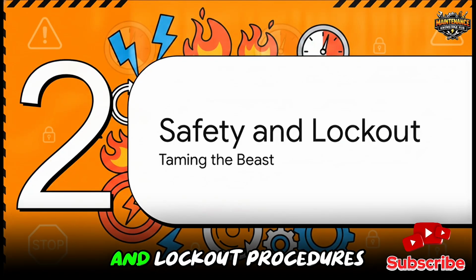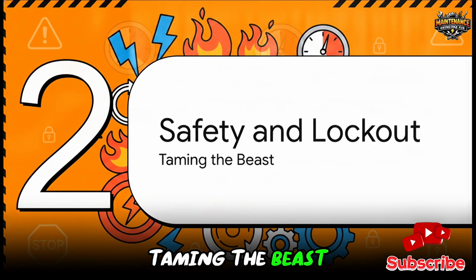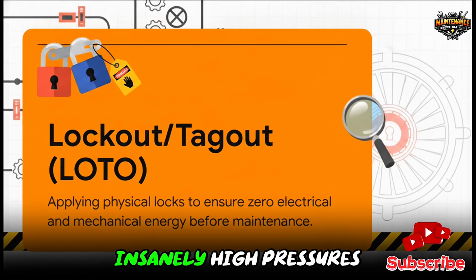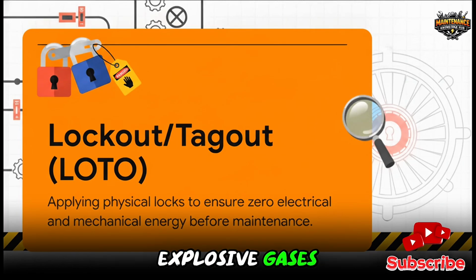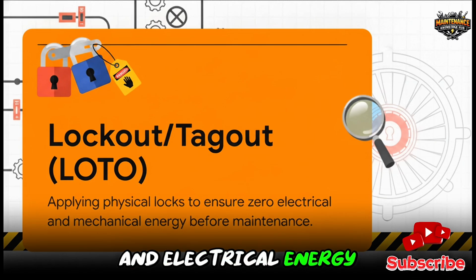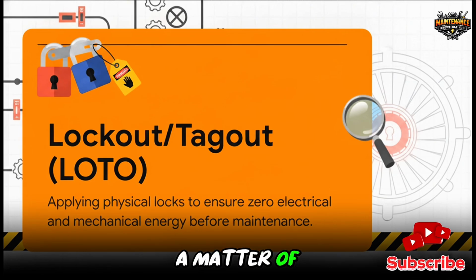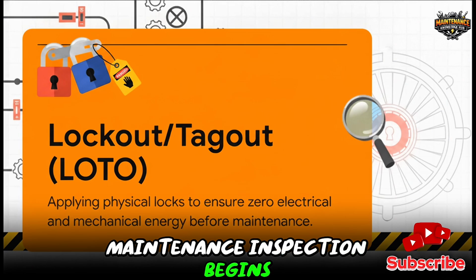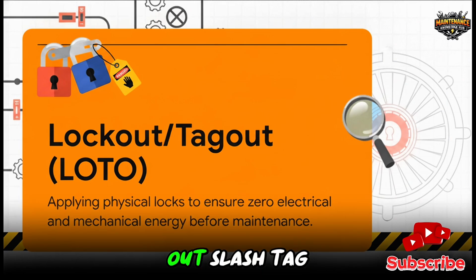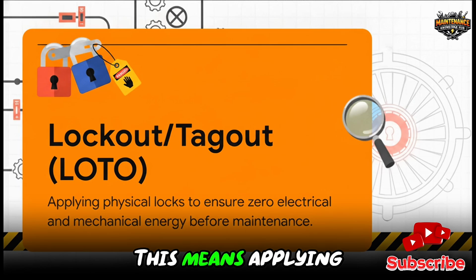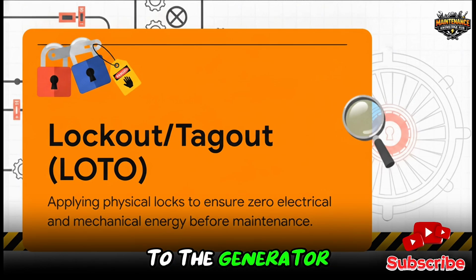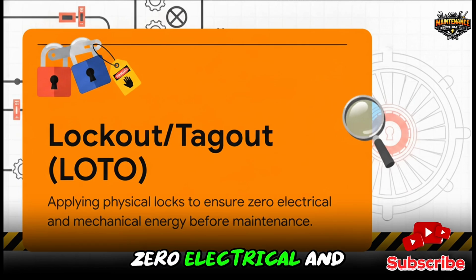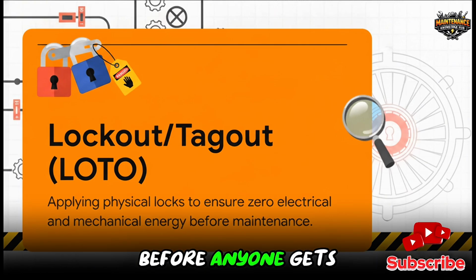Section 2, Safety and Lockout Procedures. Taming the Beast. Now, because we are dealing with insanely high pressures, explosive gases, and massive rotational and electrical energy, safety here is quite literally a matter of life and death. So the crucial point is this. The non-negotiable first step before any pre-maintenance inspection begins is the strict application of lockout/tagout, or LOTO. This means applying physical locks and warning tags to every single energy source connected to the generator. We have to ensure there is absolute zero electrical and mechanical energy present before anyone gets near it.